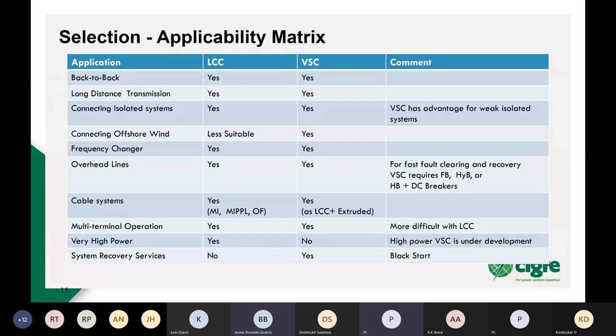For long distance transmission, in either case you can use LCC or VSC, even in the case of overhead lines. For connecting isolated systems, again, you can use either LCC or VSC. Connecting offshore wind, LCC is less suitable than VSC, because with LCC you need something to provide a system voltage supply or voltage source, whereas with VSC, of course, you can use a grid forming converter and it becomes a system frequency setting terminal and also makes the AC voltage so that your offshore wind can start and it immediately takes the power away. For frequency changers, yes, you can use either technology. Overhead lines, either technology.